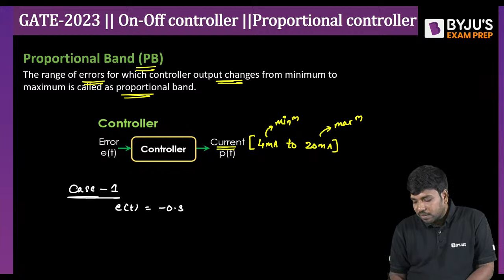What does it mean here? This means when the error is in the range from minus 0.5 meter up to plus 0.5 meter, the current value will change from where to where? 4 milliampere to 20 milliampere. Clear? So categorically, from minus 0.5 meter to plus 0.5 meter of error, the controller changes its value from the lowest possible value to the highest possible value. So this range of error, from minus 0.5 meter to plus 0.5 meter, we call a proportional band.